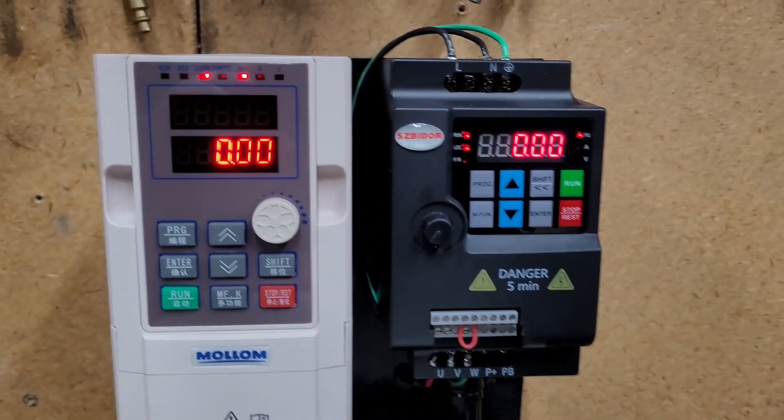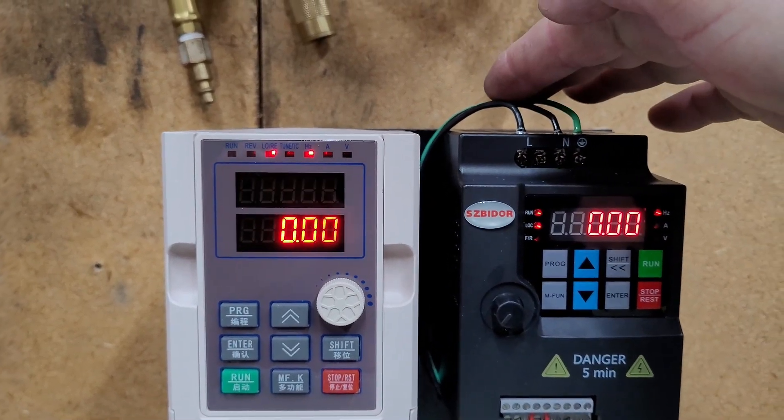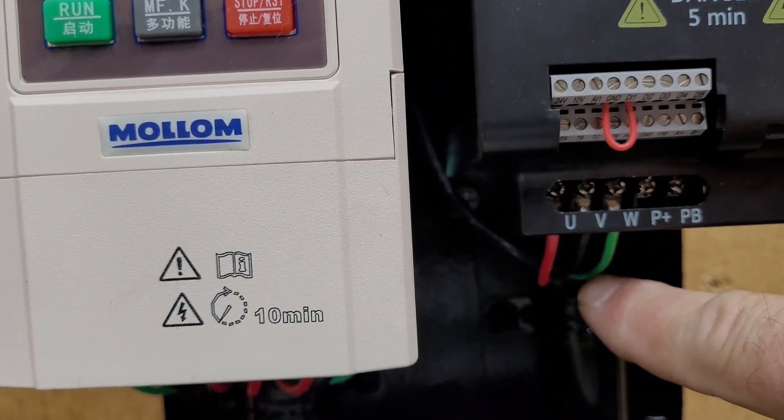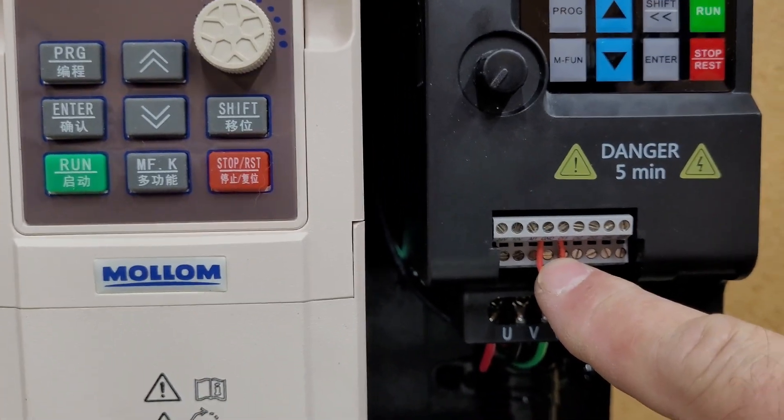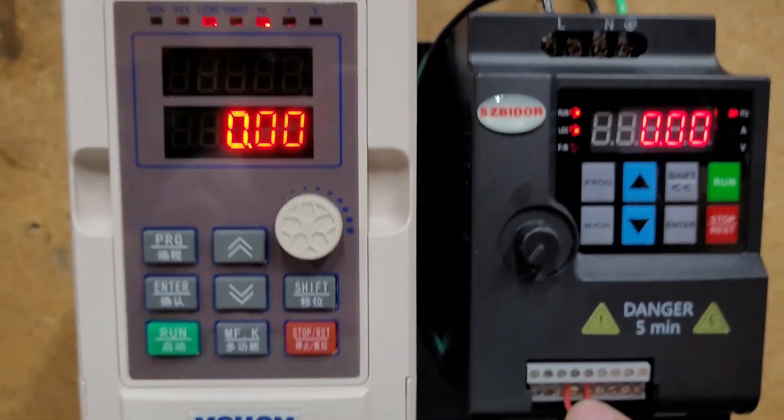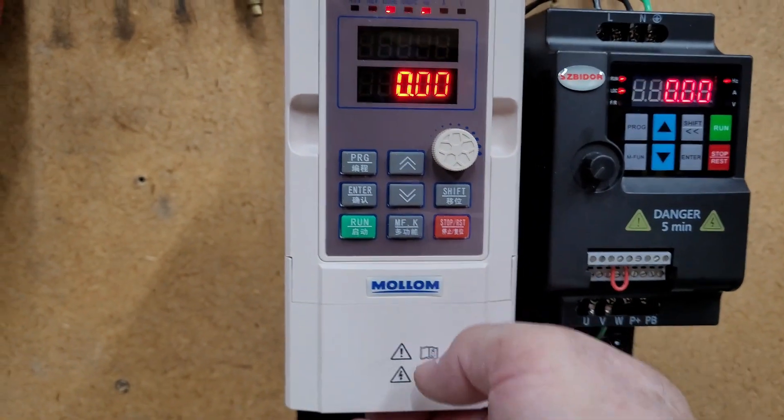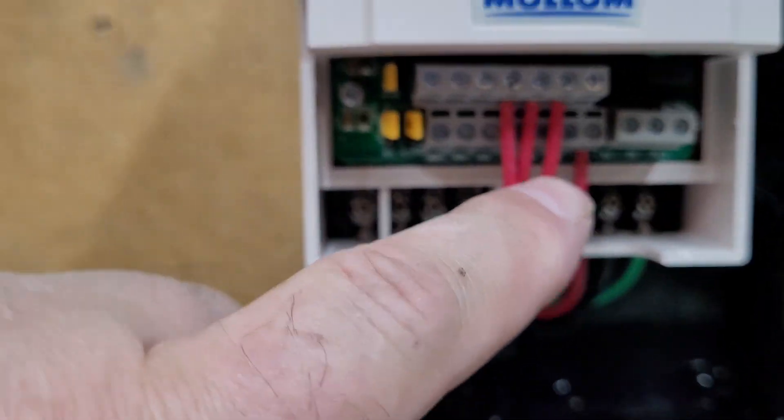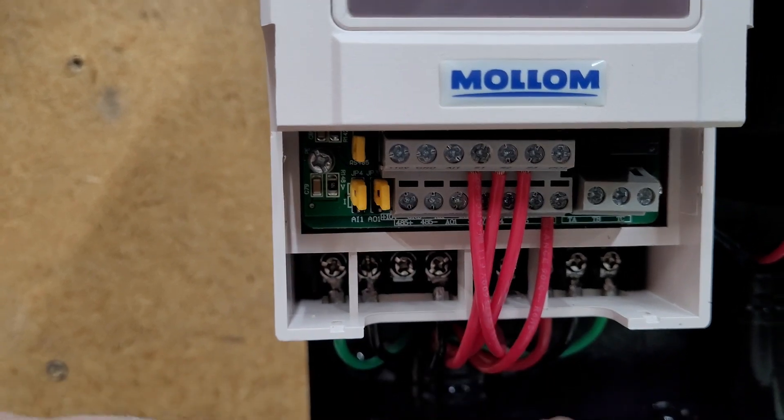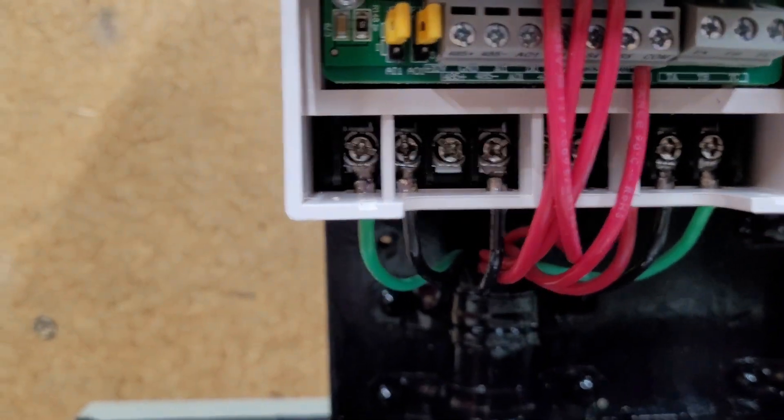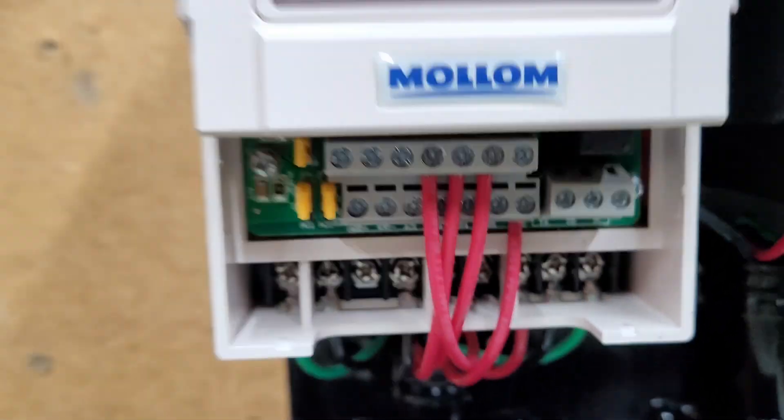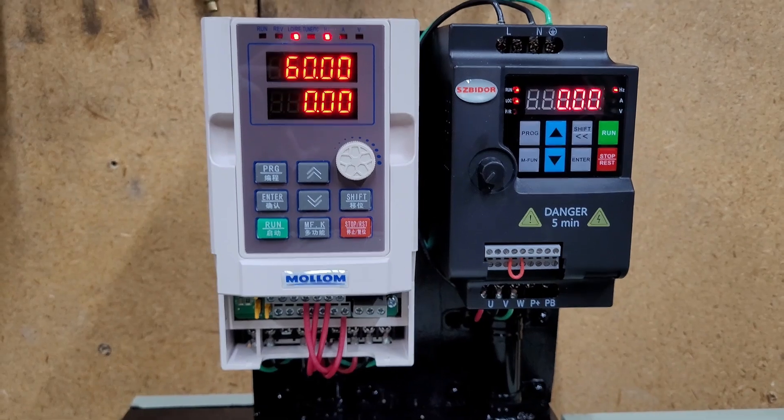On this unit, this is the 220 volt input, this is the three phases to the motor, and this is the digital input where it's configured and programmed to turn on whenever it's powered. On this unit, this is the digital input that controls the switches in the front panel and the main forward reverse for the chuck. This is ground, L1, L2 input, and then the three phases to the lathe motor. So that's how these VFDs work.